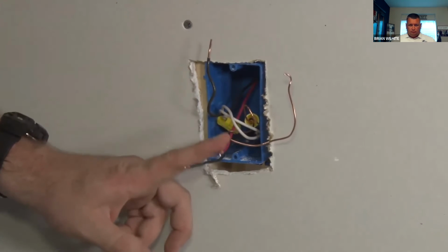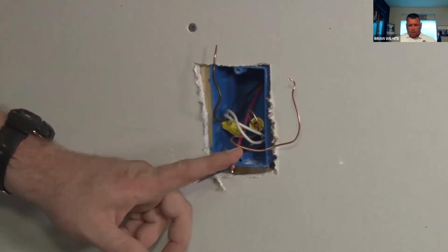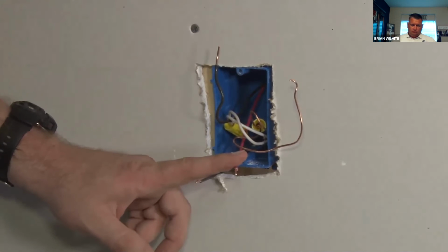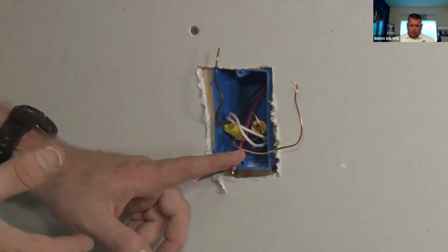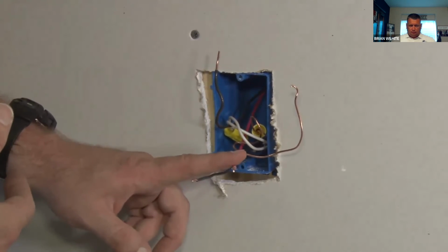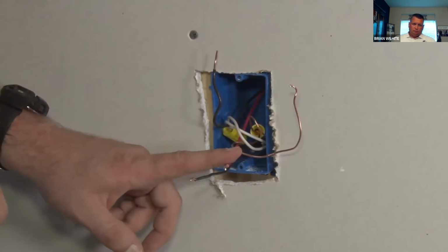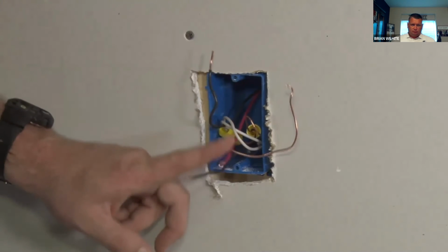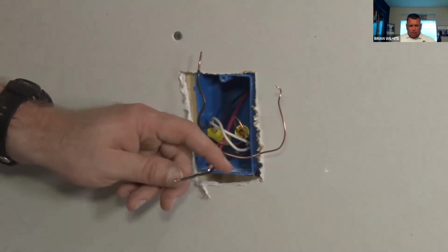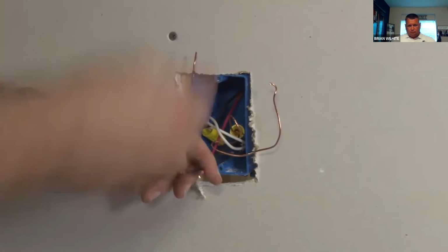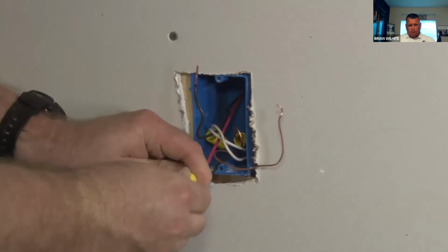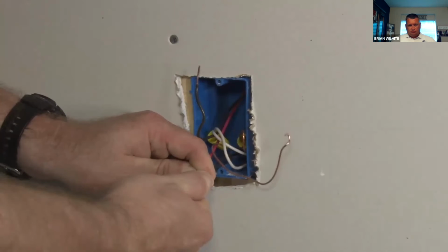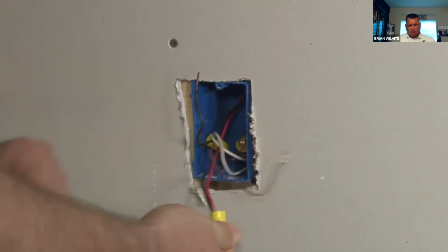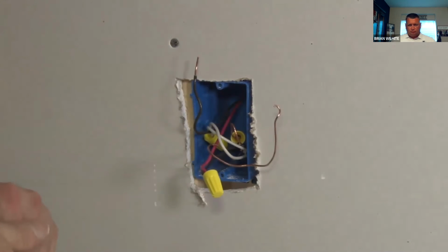I now have two other wires coming out of my first box. And in this case, I have three wires that come out of the second box. What I need to do is determine which two wires in the second box are connected to this one. So what I'm going to do is actually take a wire nut and connect these two wires together. Remember, the power is turned off and I've locked out, tagged out the circuit and verified that there is no voltage going through these wires.